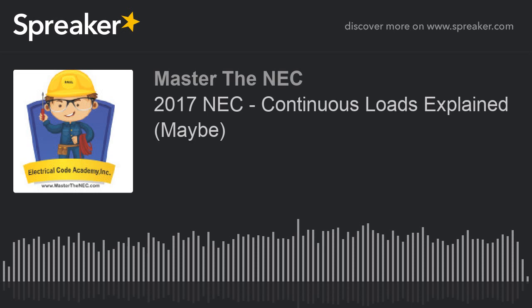Okay, so now what do we do? All right, we already know our breaker, okay? And we already know if it's a continuous load, then it can't exceed 16 amps on it. All right, we kind of went through all that. If it's not a continuous load, then guess what? I can put 20 amps on the thing. I don't want to rehearse that, okay?